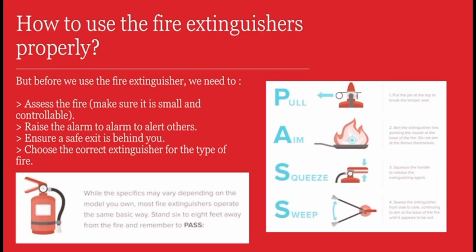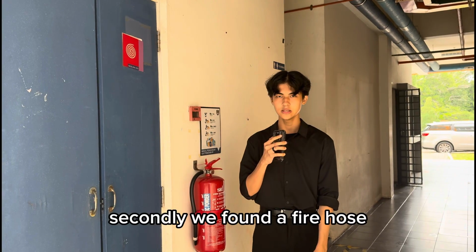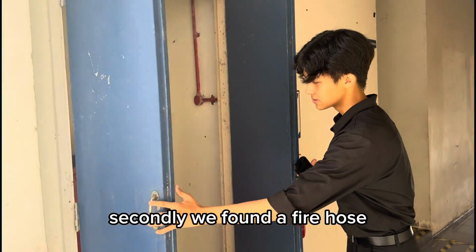What is PASS? P for pull, A for aim, S for squeeze, and the last S is for sweep. Pull the pin at the top to break the tamper seal. Aim the extinguisher low, pointing the nozzle at the base of the fire. Do not aim at the flames themselves. Squeeze the handle to release the extinguishing agent. Sweep the extinguisher from side to side, continuing to aim at the base of the fire until it appears to be out.